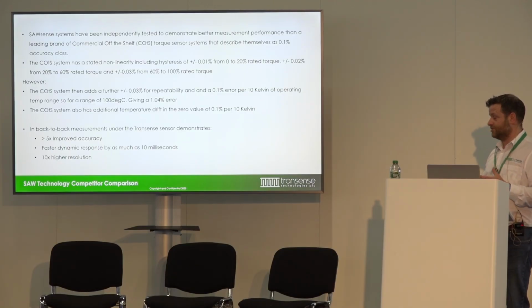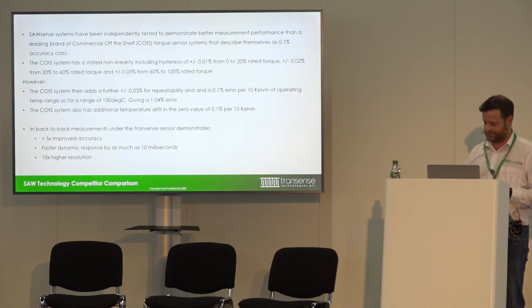And 10 times the resolution. But 10 times the resolution can actually cause you some problems, because you end up with something that looks incredibly noisy, so you often end up having to filter that down. It's a big topic in itself, and if anyone wants to discuss that, we can pick it up on the stand. The accuracy of our systems has been proven out - this work was done by an independent third-party test laboratory for us. So it's been proven out to be very good compared to more conventional measurement systems.